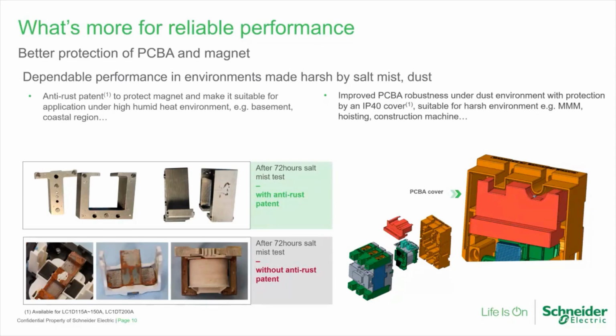Similarly, as I mentioned earlier, we have used electronics inside this contactor. So there are two electronics parts. One is electronic coils, and second is electronic circuitry, which is used for building the algorithm. Now this electronic circuitry has been protected by providing covers. These are IP40 covers, and because of these covers, you can very well use these contactors for your steel applications, for triple M segments, even for hoisting or construction or cement industries. This cover is definitely going to help avoid all the conductive dust which is going to get settled on PCBs. And definitely we can say that you can very well use these contactors for all your triple M and hoisting applications.